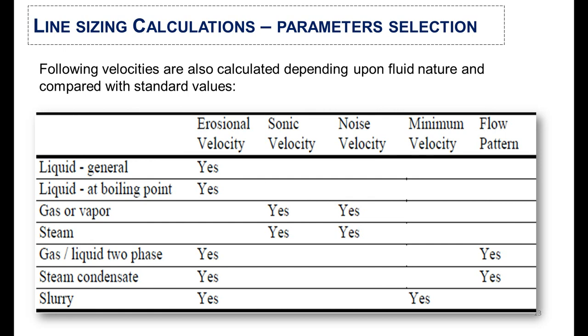The following velocities are also calculated depending on the fluid used as the service medium for your pipeline. For liquid fluids, erosional velocity is the major concern. For gas or vapor, there is sonic velocity and noise velocity to calculate. For slurry flow fluid, you must calculate both minimum velocity and erosional velocity.